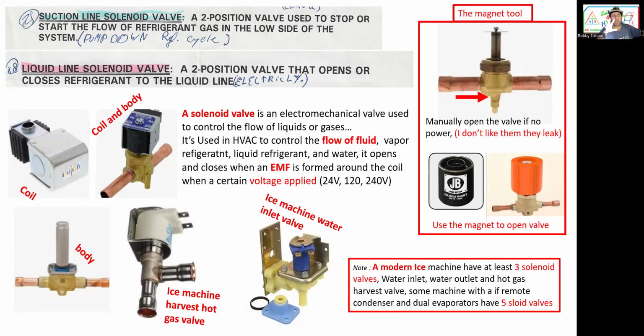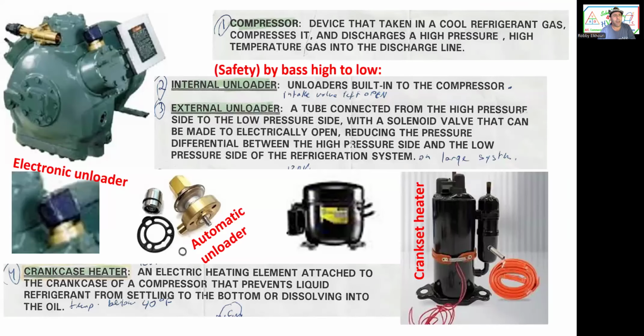All right, next, I put the compressors, unloaders, external unloaders, and crankcase heaters all together for this video. And the compressor, we know what it is, the heart of the system, a device that takes in vapor refrigerant and discharges superheated gas to the condenser, right? It's the heart of the system. It's a pump. It's a vapor pump, remember. And we have 5 kinds of compressors.